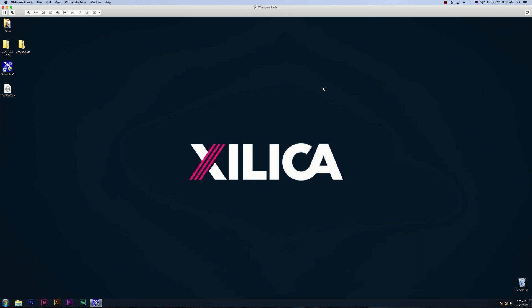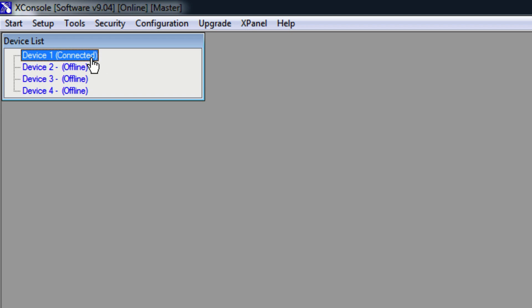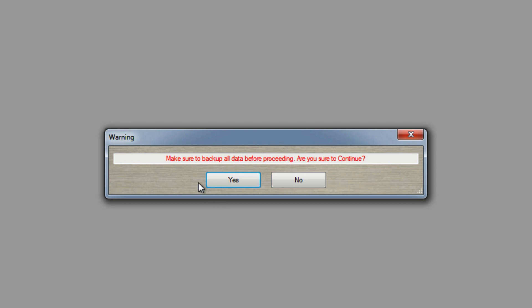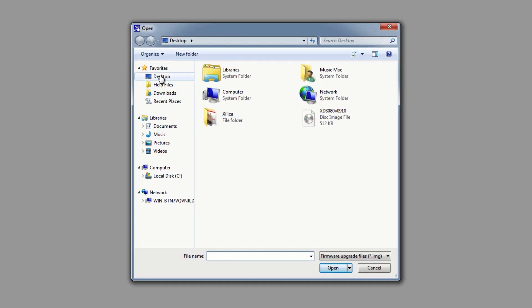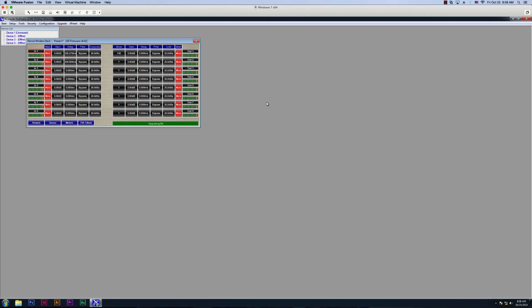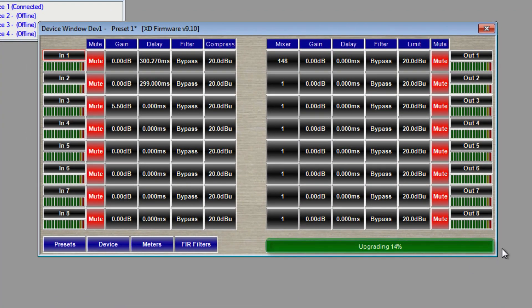When upgrading the device, use USB connection. Open up your software. Make sure that your device number is connected and highlighted. Then go up to the Upgrade tab and click on Firmware. Upgrading firmware will erase all data from the device, so we recommend backing up and saving your data from your device before proceeding. Click Yes to proceed, then select the disk image that you extracted from the firmware file. At the bottom of the device you'll see a green bar — this is the device status, giving you information about the status of the device. Make sure you do not power off your device during this process. Doing so can corrupt your processor.